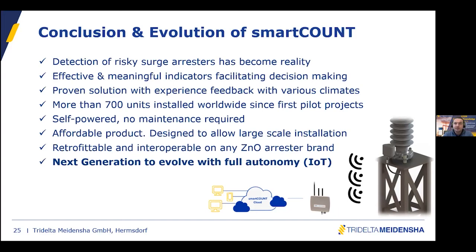From my experience in the surge arrester industry, it's always a kind of challenge when you install a monitoring device and then you have some values and you don't know what to do with those values. So this is important. If you have a look at the user guide, if you read some technical papers that Philip Raschke made, we are trying to give you some rationale to take decisions based on the current values and especially the trend of the currents, the patterns of the currents.